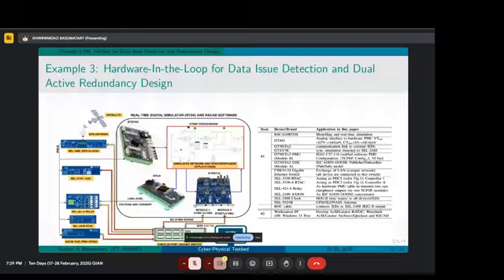In the same way as we did with the SEL-751, we are also injecting the simulated voltage and current to the SEL-421 via low signal interface. The process was the same as while integrating the SEL-751. And the RTDS GTNET-X2 has two modules, module A and module B, which means that when we simulate, we can take two protocols.